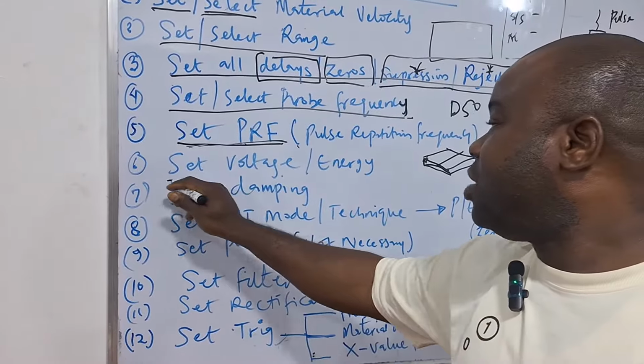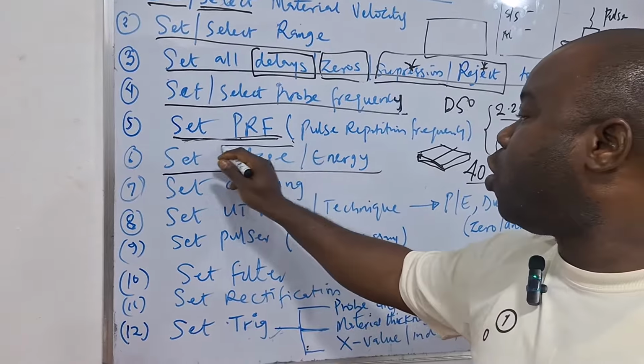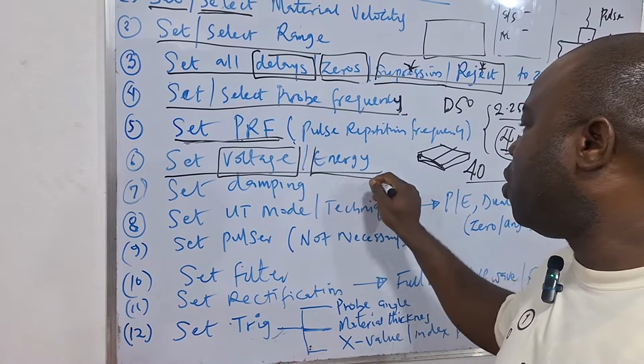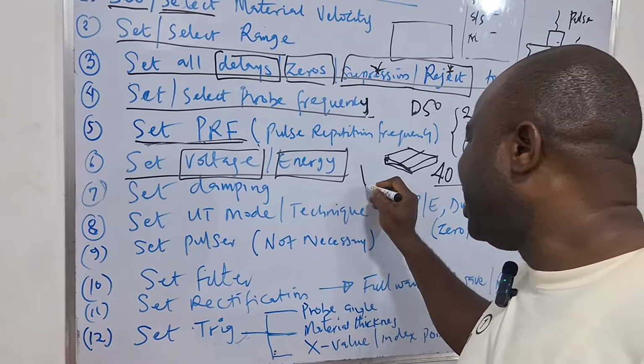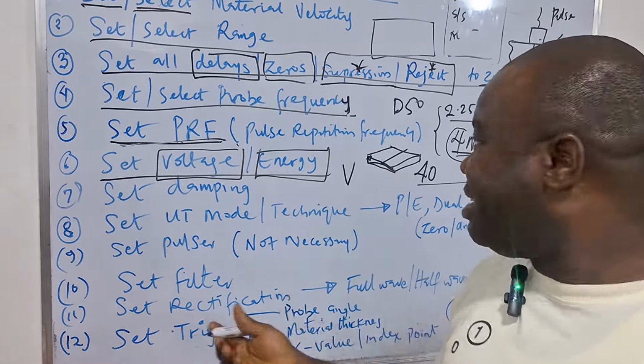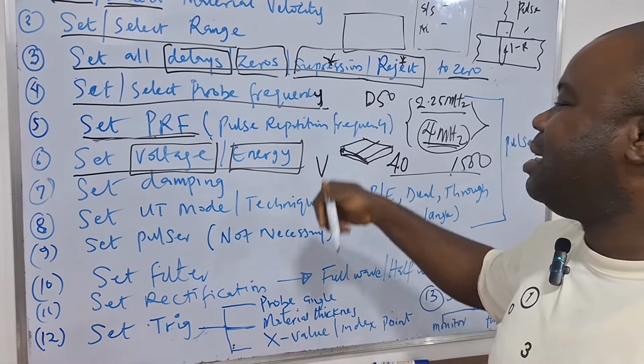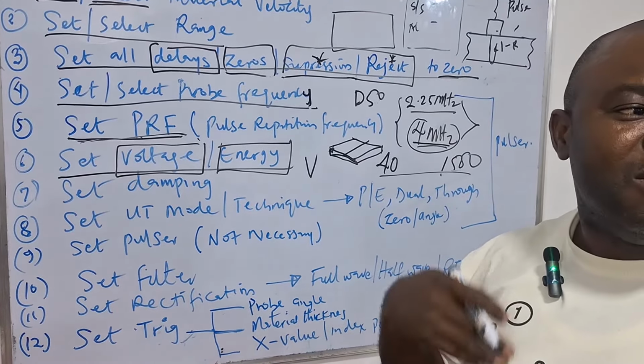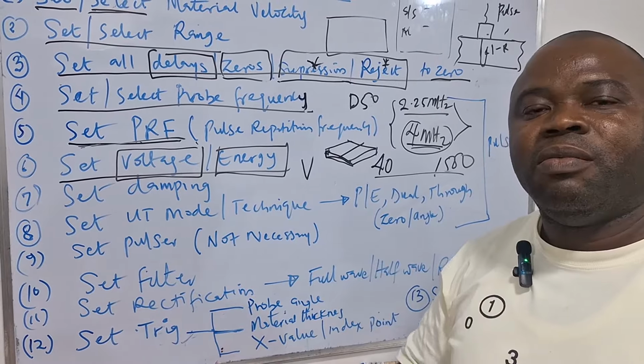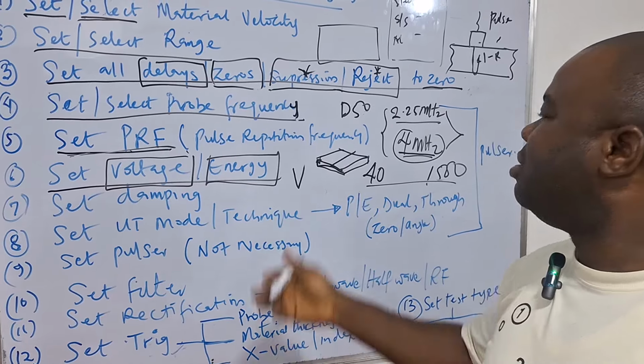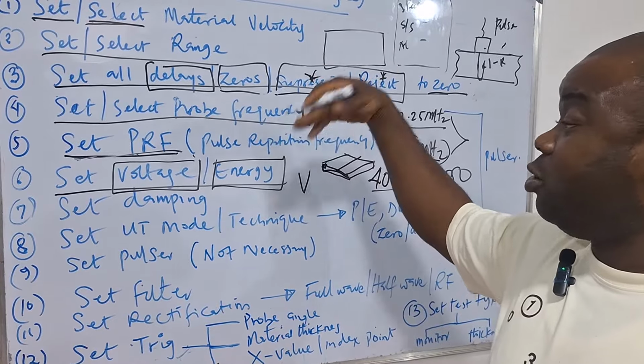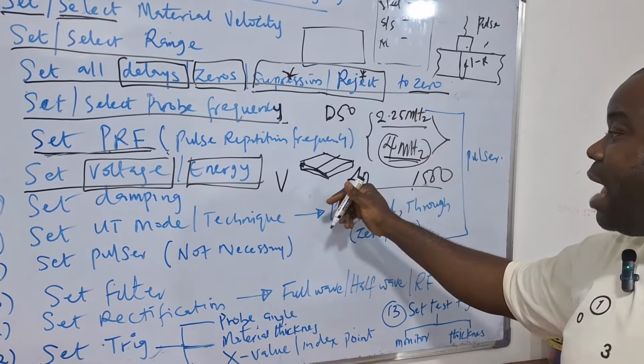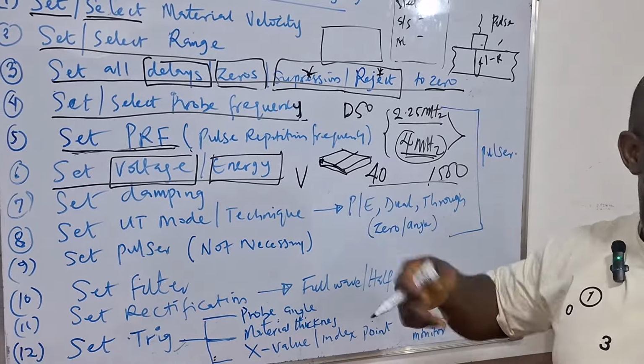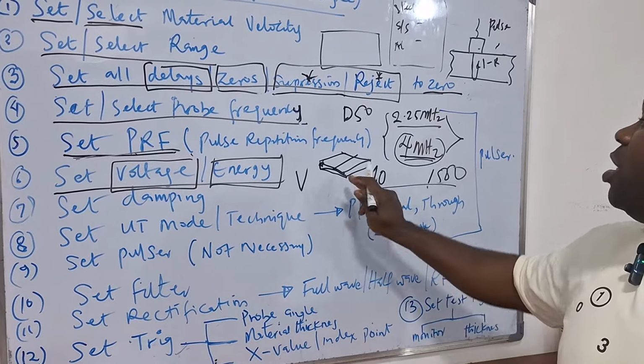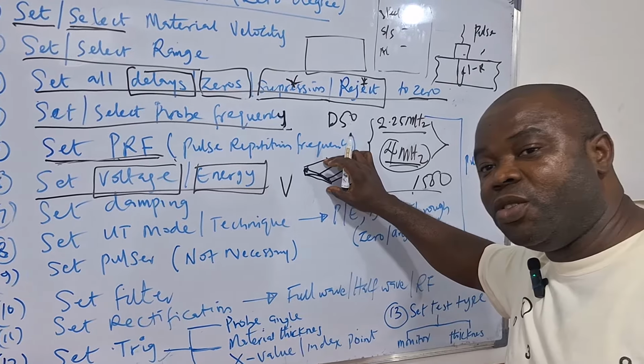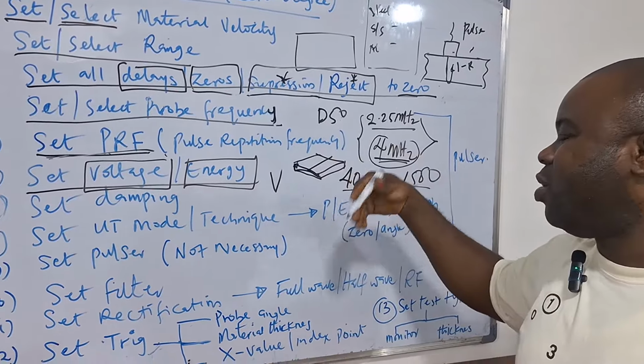After setting PRF, the next thing you want to set is voltage. Some units will call it voltage, while some other units will call it energy. The unit is usually volts. It is the same concept as with frequency. The higher the voltage, the more the vibration, the more the energy that is being used. And you want to keep the voltage low, because if the voltage is very high and I have a very thin crystal that is consuming so much voltage, it can lead to breakage of the unit and can also generate noise too.